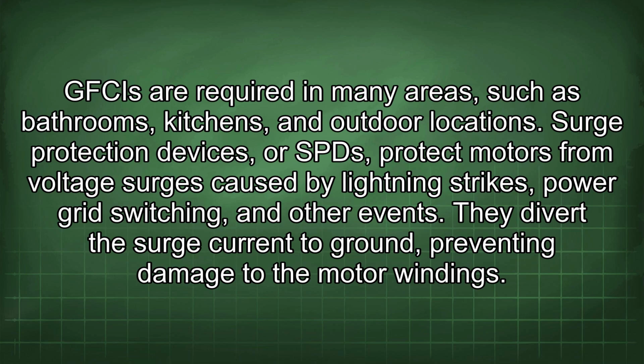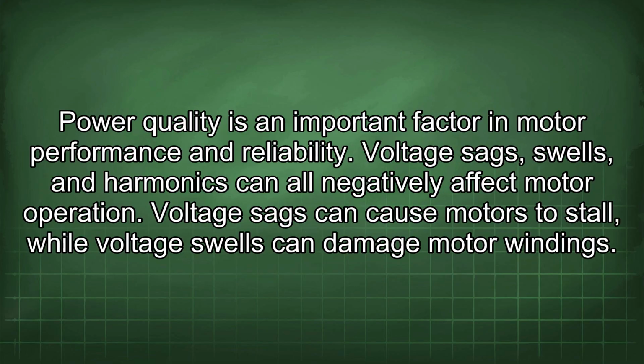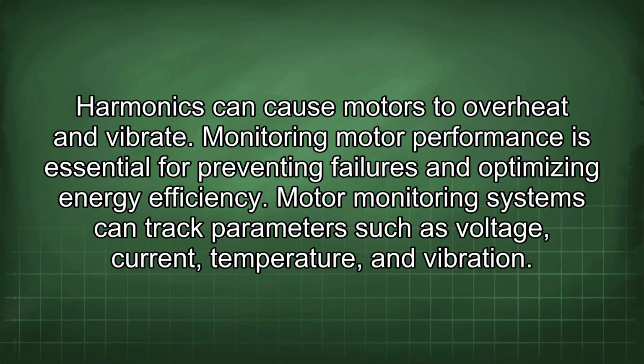Surge protection devices, or SPDs, protect motors from voltage surges caused by lightning strikes, power grid switching, and other events. They divert the surge current to ground, preventing damage to the motor windings. Power quality is an important factor in motor performance and reliability. Voltage sags, swells, and harmonics can all negatively affect motor operation. Voltage sags can cause motors to stall, while voltage swells can damage motor windings. Harmonics can cause motors to overheat and vibrate.